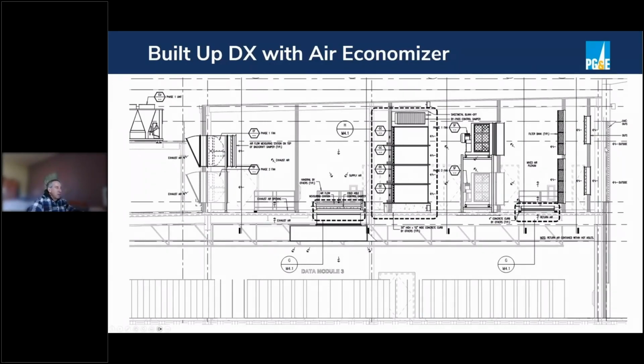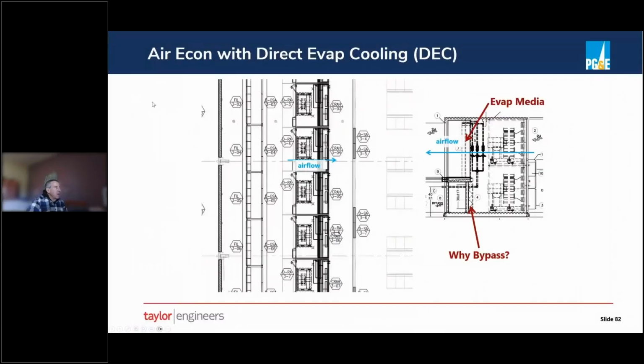So, a very efficient design because it's got an air economizer, right? We've got our outside air, return air, and our exhaust relief system, no water, right? Air cooled. It still has a relatively high peak PUE because we're air cooling with DX, but it's generally very efficient because of the air economizer.